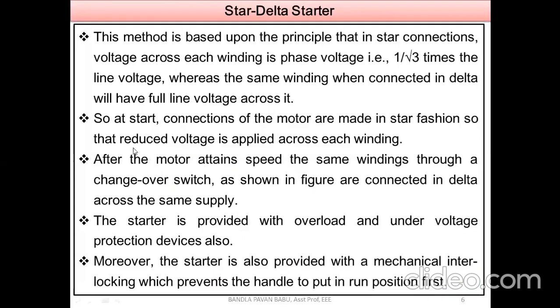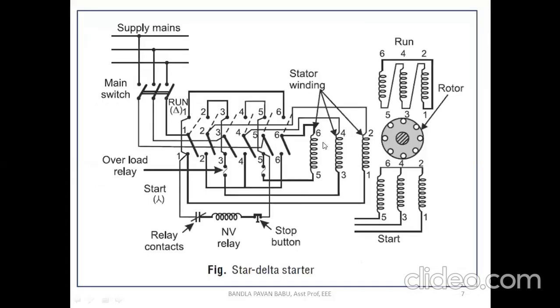Once again we will recall what has been done. At the start, we connect the star connected winding. After the motor reaches the rated speed, or its final value, with the help of the changeover switch we connect it to the delta. So it is a simple thing, only two cases. At the start the machine is connected in star, and after it reaches the rated speed, it is connected in delta with the changeover switch. So let us see the procedure here.